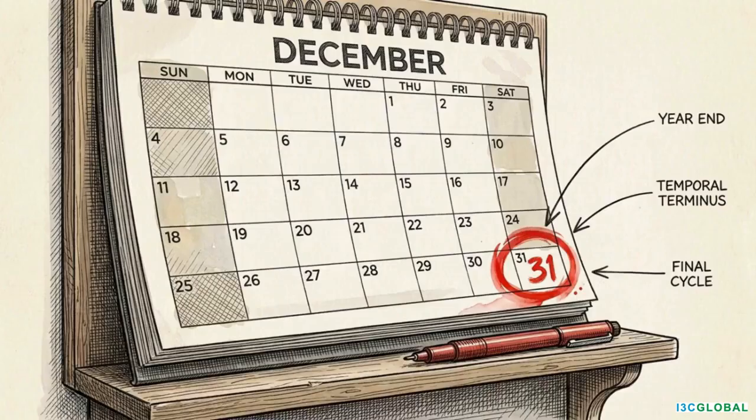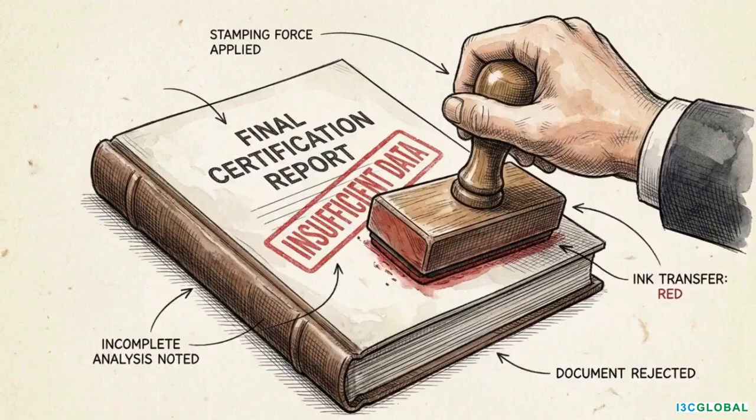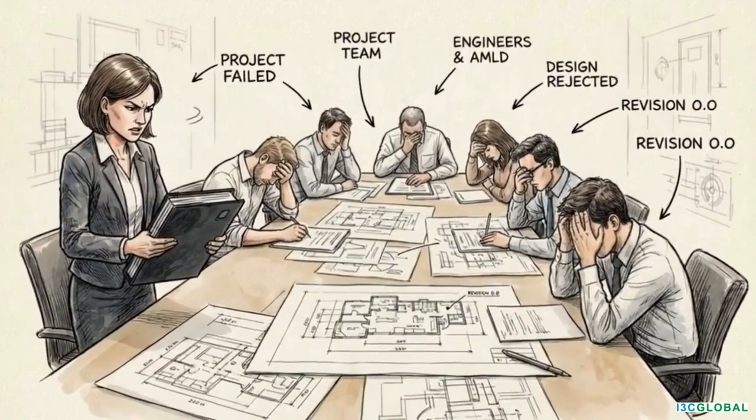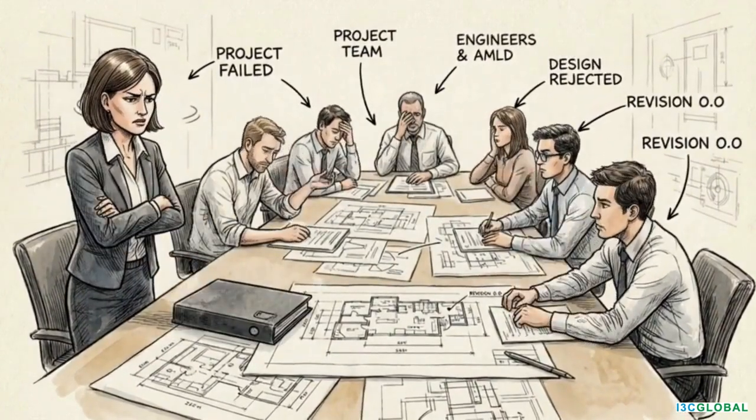While these rejections happen at the end of the process, they are the direct result of how the manufacturer structured their data collection months or even years earlier. When a notified body identifies a weak literature search or a poor equivalence claim, they are pointing to a failure in the clinical evaluation plan. If the plan doesn't define these parameters correctly at the start, the final report cannot meet the legal threshold for certification. Neglecting the strategic details of the clinical evaluation at Step 1 essentially builds the entire MDR certification process on a flawed premise.